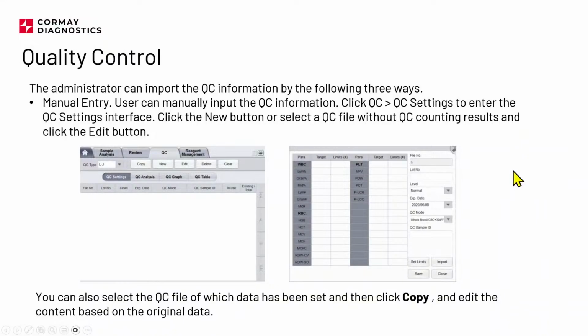Quality control. So in the quality control menu, we have settings, right? So this is the first window where you need to go in order to set up new targets and ranges for your QC analysis. So QC settings, and then you need to press on new. And this window will actually appear. So what you can do, since this is for hematology, we can choose from QC mode, whole blood, CBC, 3diff, but we can also choose the CRP mode, and in the CRP mode only the CRP parameter will be present here.